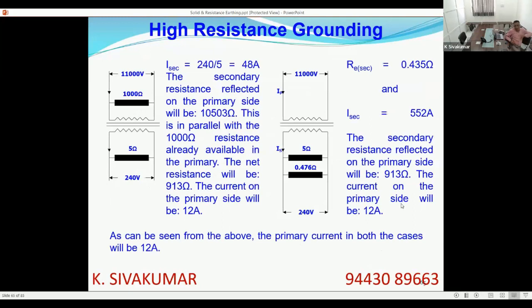So this is the one you are talking about. I have not, per se, exactly added a neutral earthing. I just wanted people to understand the theory that when you connect a very low value resistance on the LV side, it will be reflected as a very high resistance on the HV side. This is the basic transformation theory. That is why with any load you connect, even though the secondary current is more, the primary current is very, very less, because the low resistance added in the secondary appears as a very high resistance in the primary. So the HV side current is always lesser.